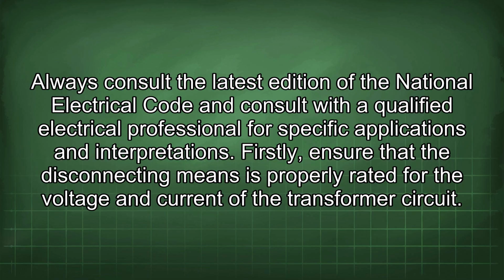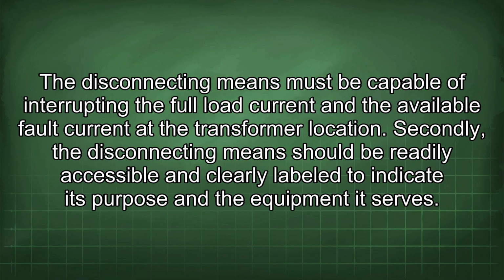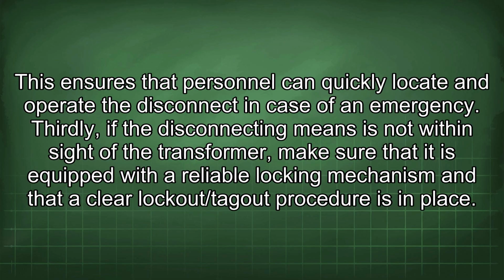Firstly, ensure that the disconnecting means is properly rated for the voltage and current of the transformer circuit. The disconnecting means must be capable of interrupting the full load current and the available fault current at the transformer location. Secondly, the disconnecting means should be readily accessible and clearly labeled to indicate its purpose and the equipment it serves. This ensures that personnel can quickly locate and operate the disconnect in case of an emergency.